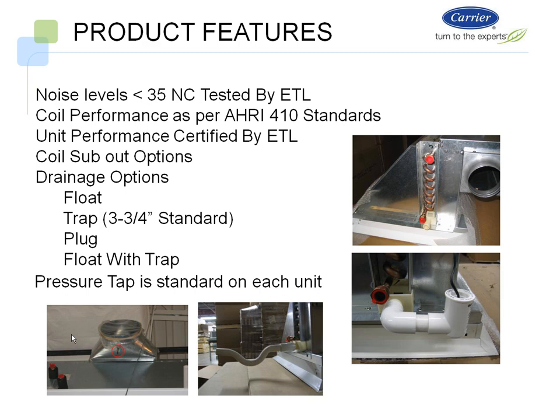Also, just drawing your attention over to the far right picture there of the float with the trap. We put that float switch in there, and that float switch is actually settable. Versus that paddle switch, which tends to be unreliable, these are much more reliable, as well as being in conformance with UL 508. But this device also allows you to set it.